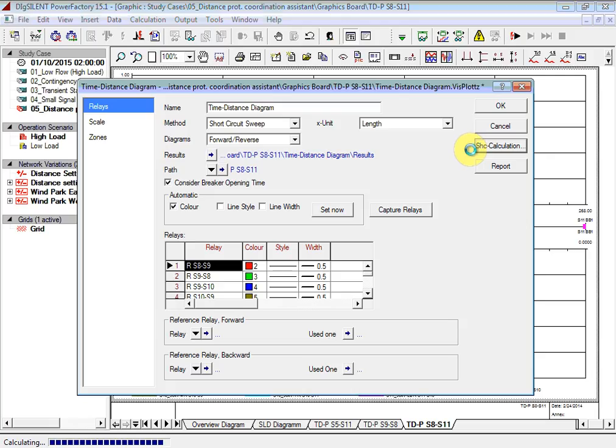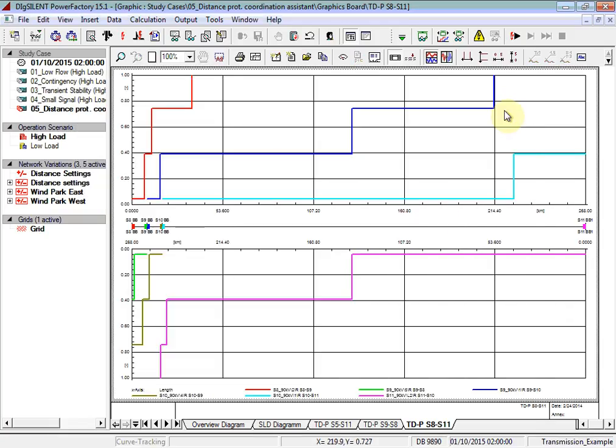and in the background you can see that the short circuit calculation has been carried out. Select OK. Here you can see the time distance diagram for the path, taking account of the real settings that have been applied to the relays. These diagrams could be further adjusted by altering the starting block settings for the respective relays.